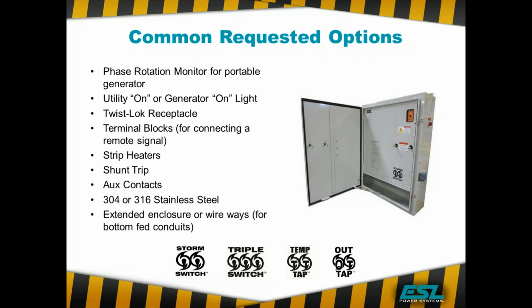We can put strip heaters inside the unit, and they serve a dual purpose. Down in the Southeast, a lot of units have heaters in them to control humidity inside the unit so you don't get water condensation. In colder climates, they're used so that the door doesn't freeze shut. So those are somewhat popular depending on your location.